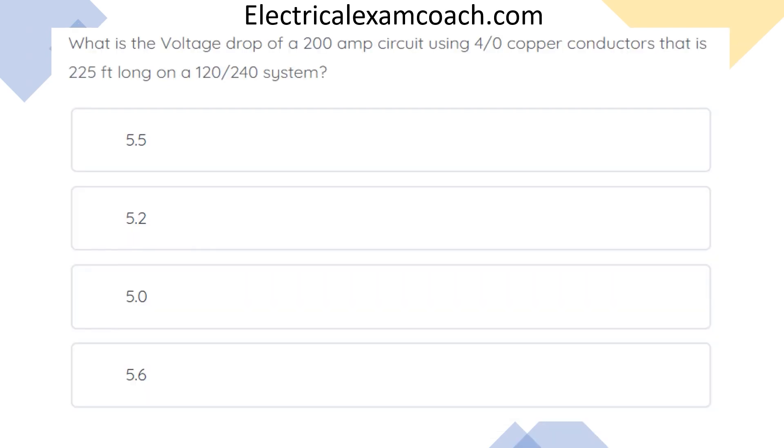What is the voltage drop of a 200 amp circuit using 4-aught copper conductors that is 225 feet long on a 120-240 volt system? And the correct answer is A, 5.5.